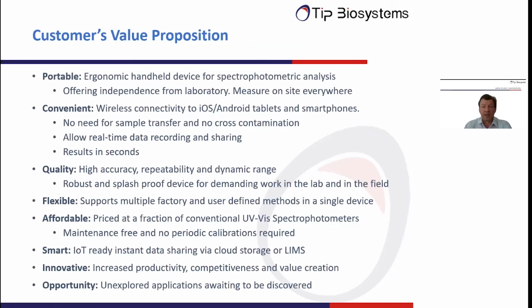So what you get as a customer from the Photopette technology is ultra-high portability. It's an ergonomic handheld device for spectrophotometric measurements of high quality, independent of a lab, so you can measure everywhere on site. It's very convenient. It's wirelessly connected via Bluetooth, either to your tablet or smartphone. There's no need for sample transfer, and there is no cross-contamination when you are changing the cuvette tip. It allows real-time data recording and sharing, and everything is very fast, with results in seconds. The quality, repeatability and dynamic range of the device is very good, and it's robust and splash-proof.